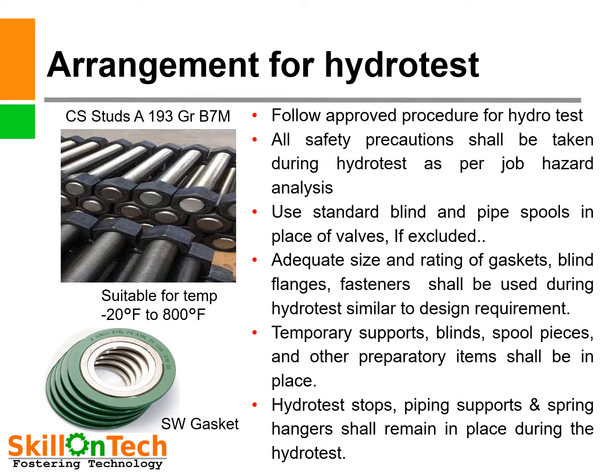Follow the approved procedure for hydrotest. All safety precautions shall be taken during hydrotest as per job hazard analysis. Use standard blinds, flanges, and pipe spools in place of valves if excluded. Adequate size and rating of gaskets, blind flanges, and fasteners shall be used during hydrotest similar to design requirements of the pipeline. Temporary supports, blinds, spool pieces, and other preparatory items shall be in place. Hydrotest stops, piping supports, and spring hangers shall remain in place during the hydrotest.